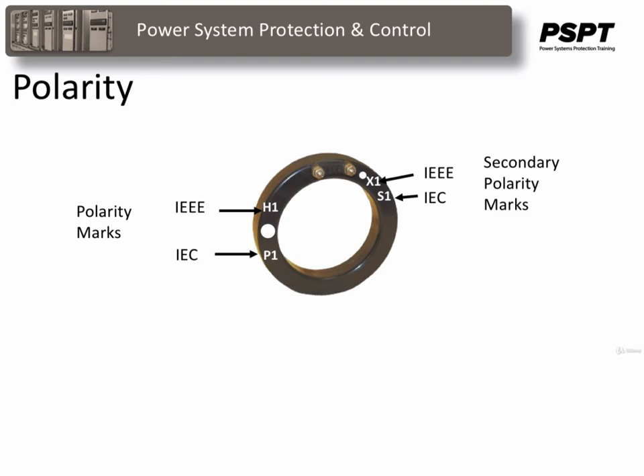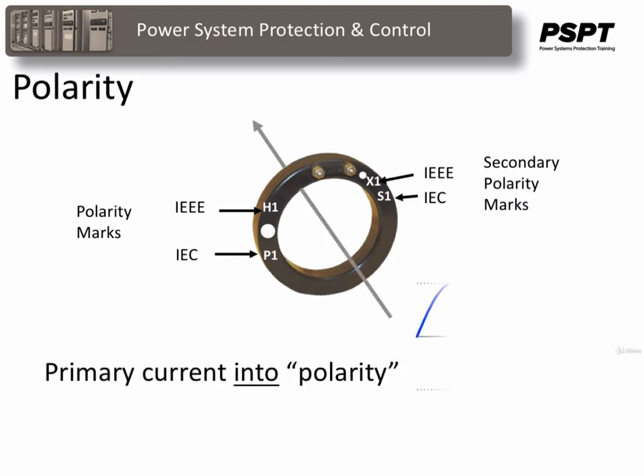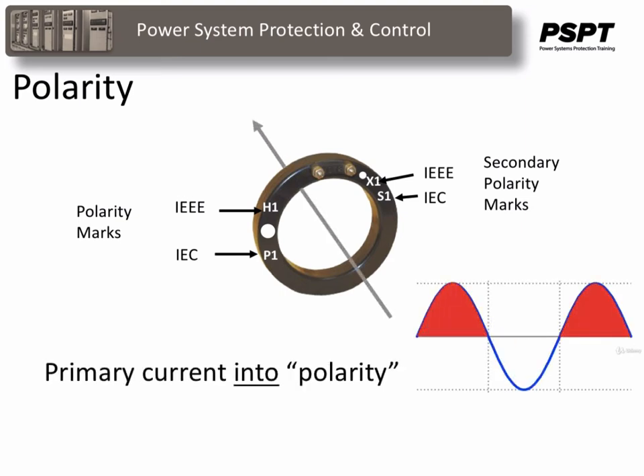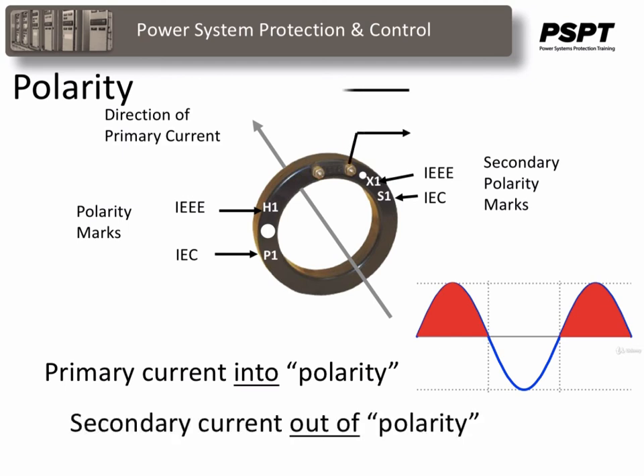So what does this mean? This indicates that when the primary current is positive during the sinusoidal half cycle, or the current is flowing into the spot on the primary, the secondary current will be out of the spot on the secondary. Okay? So the primary current is positive during the sinusoidal half cycle, or current is flowing into the spot, then the current will be flowing out of the spot on the secondary.